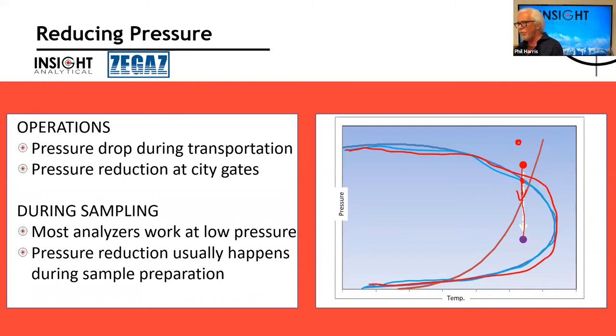Because of the shape of this curve, they do things a little bit differently in Europe than we commonly do here. Europe focuses more on dew point and less on concentration. And so in Europe, there's a point on the phase diagram, a temperature where the belly of that phase diagram sticks out the most. And they say, what we're going to try to have you do is adjust the pressure in your pipeline, and adjust the pressure of your sample as it goes to the analyzer, so that you're always operating around that belly where it's sticking out. So that's going to be the highest dew point temperature you could possibly achieve for this gas.